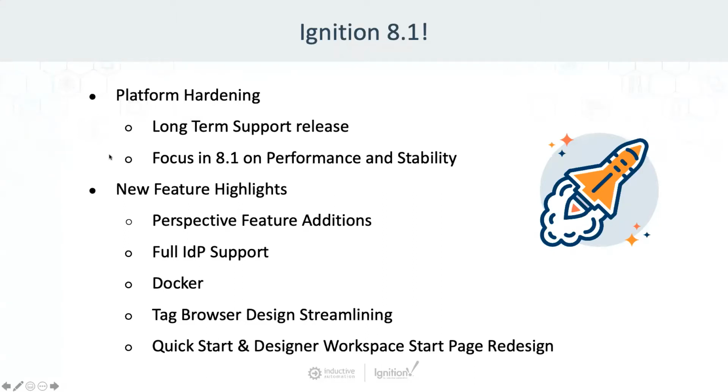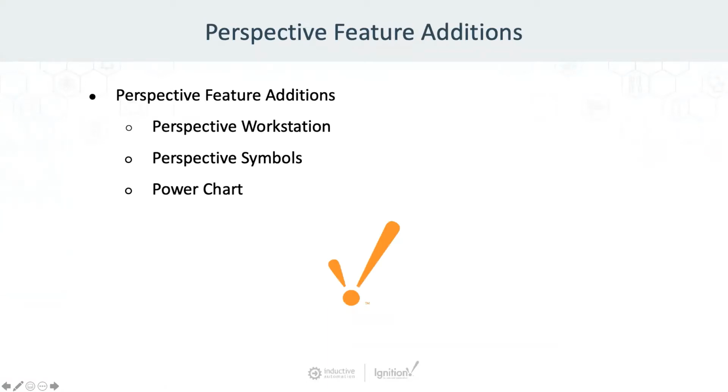Among the features that they've added to Perspective, they've added the concept of Perspective Workstation. This is very exciting because, as you know, Perspective was an HTML5 browser-based client, so you log into your session for your SCADA solution in your browser. But there was no way to stop the operator from opening up another tab or going into the Windows menu. Now they've created a little app, which they call Perspective Workstation, and I can launch my Perspective project in such a way that it locks out the window, and I can't get the operator to navigate to different tabs in the browser, etc.